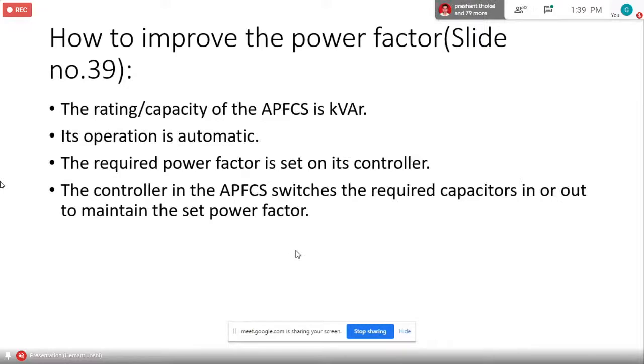How to improve the power factor? Continue. The rating capacity of the APFCS is in kVAR. Its operation is automatic. The required power factor is set on its controller. I will show you the controller. The controller in the APFCS switches the required capacitors in or out to maintain the set power factor. So the controller senses the power factor, and depending on that it will switch in additional capacitors, or it will switch them out. If the power factor is way higher, it will switch out. If it looks like it's going down, it will switch in.